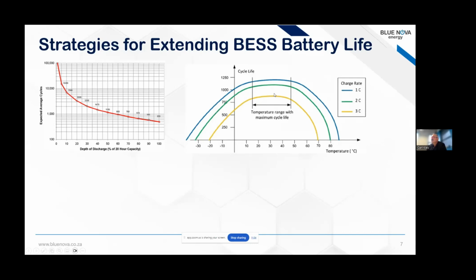And also with a higher capacity, that's why typically we do not recommend using a battery higher than 1C, ideally actually half a C, which gives you an optimal lifetime on the battery.